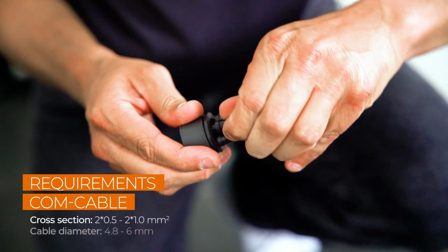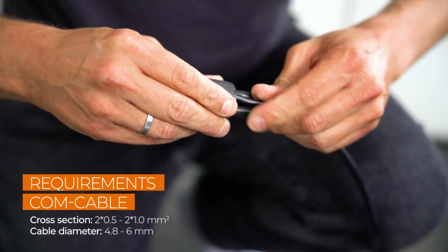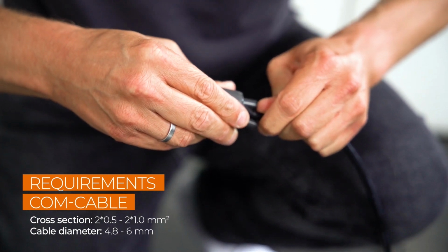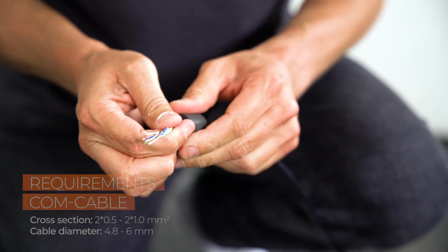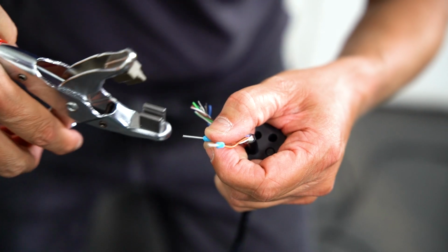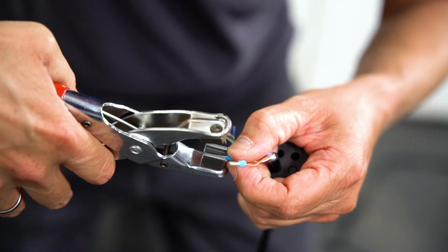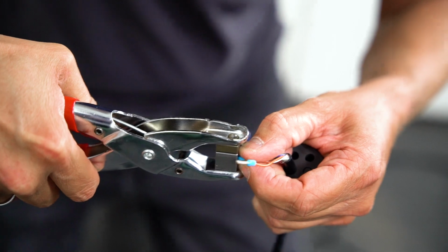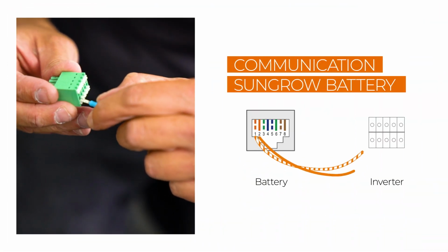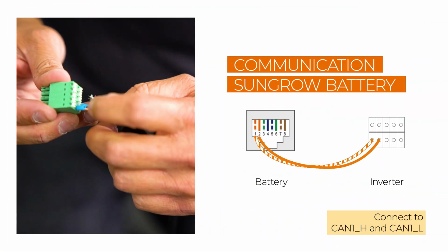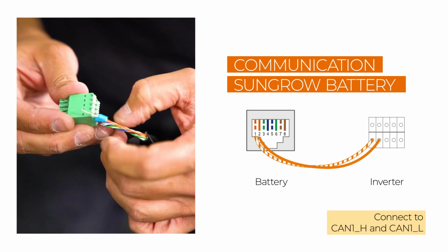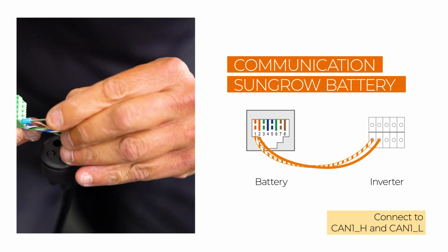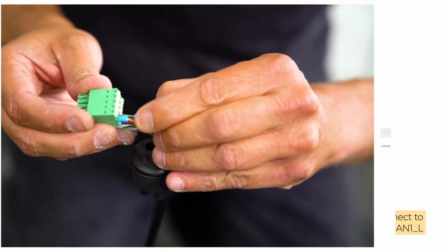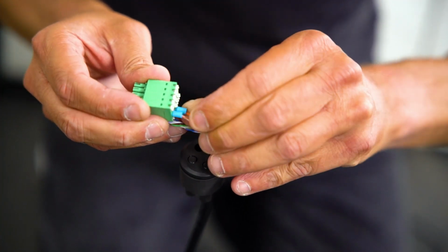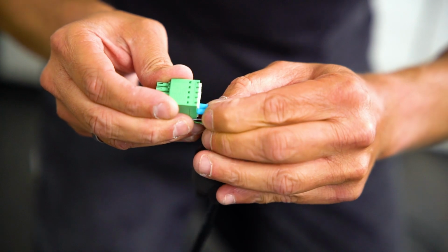Remove approximately 4 to 5 centimeters of the cable sheath of the communication cables. Then strip approximately 5 to 7 millimeters of the inner cables. If necessary, you may have to fit the cables with end sleeves before you push them into the plug. The Sungrow battery is connected to the CAN interface. You may find a detailed installation video for our battery on our YouTube channel. The BYD battery is connected to the same ports.